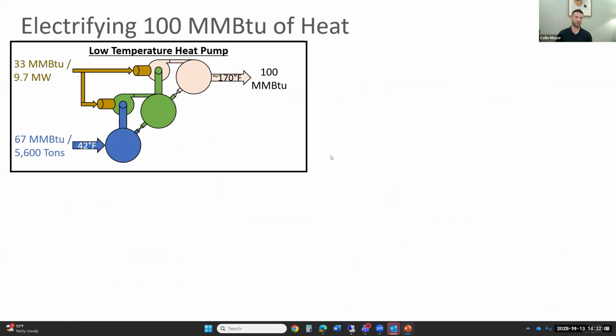Looking at the heat pump a little bit more specifically, as far as how it uses energy to move that heat from low temperature to high temperature, the amount of work that needs to be done is going to change at different temperatures. So if you have what we call a low temperature heat pump that could be delivering about 170-degree hot water while it's sourcing heat from something similar to chilled water temperatures, you're going to have a COPH there of around 3. It's going to depend on what type of compressors you have and exactly how the machine is designed. But you're basically going to generate 100 million BTUs per hour of heating by recovering 67 million BTUs per hour of cold thermal energy and using 33 units of work. So the work and the cold are combined into the hot.